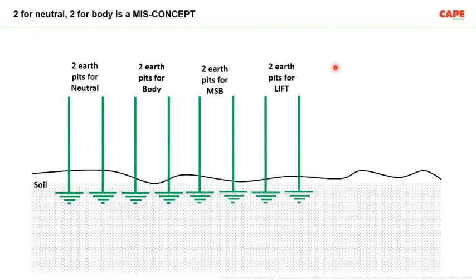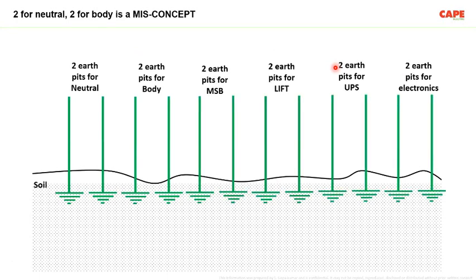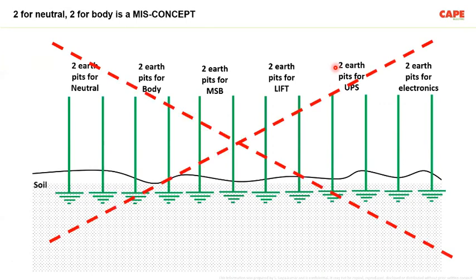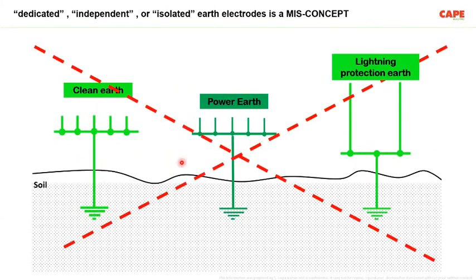The biggest misinterpretation happening in India is, I always call it a joke, 2 for neutral, 2 for body. There is nothing called 2 for neutral, 2 for body. It is a totally big mistake, totally wrong. You should not follow this particular concept. You will invite a problem. Similarly, systems like clean earth, meaning connecting the earthing of all the electronic items together to an earth electrode in soil, power items connecting separately to an earth electrode in soil, and lightning protection separate, is also a big mistake. Please don't follow it.